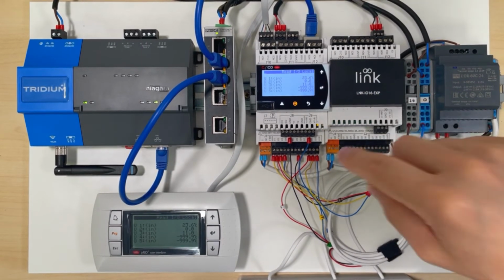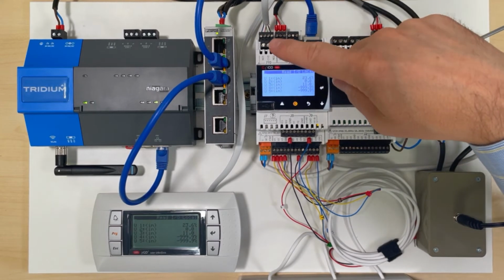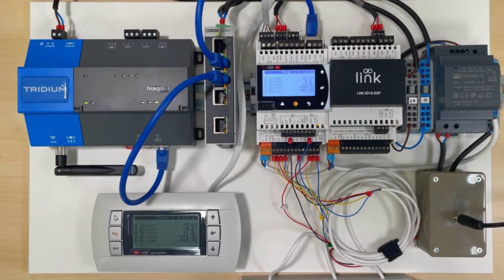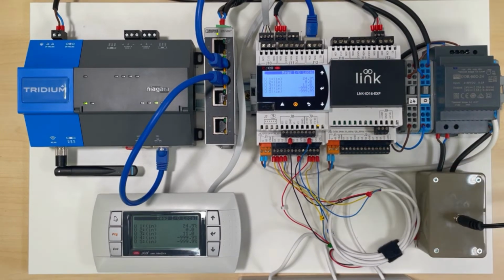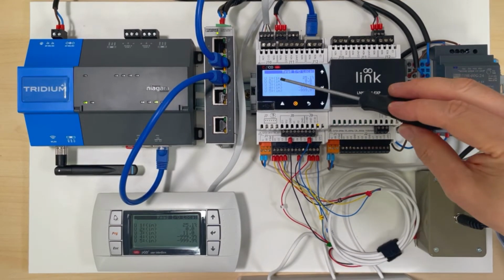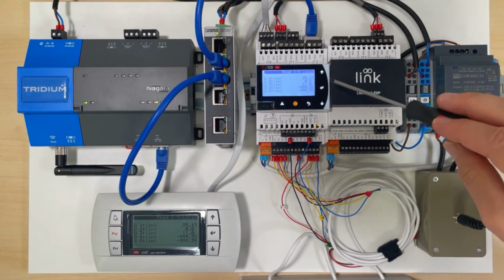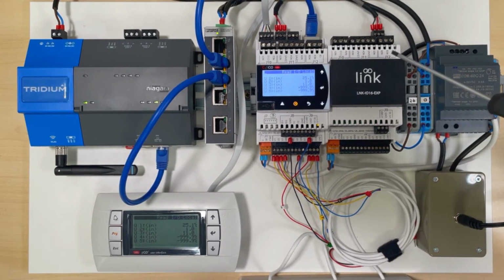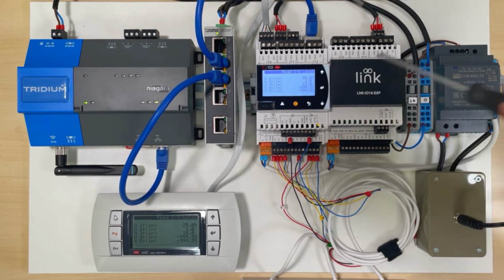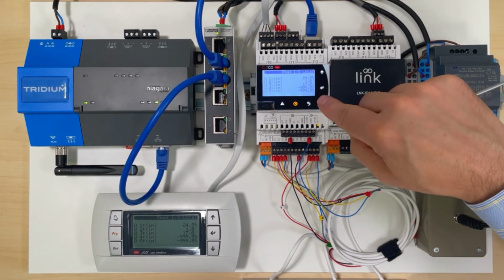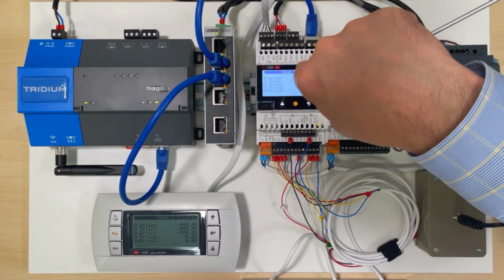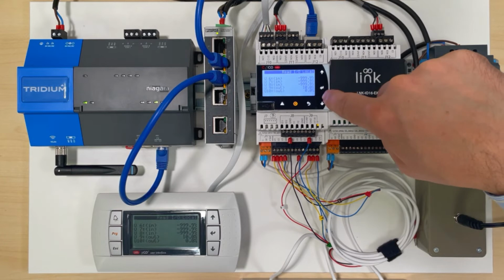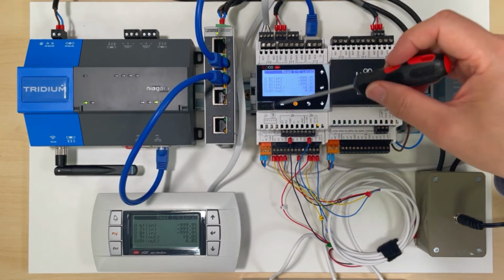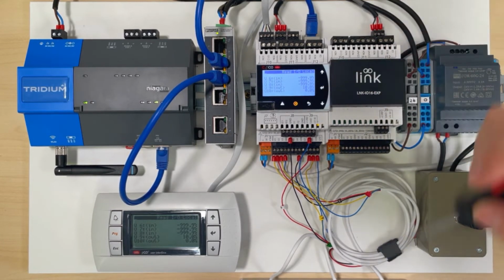So what you notice here is I've got U1 set up as 10K3A1. I could warm that up, and what you notice is it responds very quickly actually. I've got a U2 set up as a digital input, it's just on or off. U3 I've set up as pulse count, just put a few pulses into there and it will count up, and so on and so forth. If we go down, what you notice is in brackets against each universal I/O point, it tells you if it's input or output, so that's quite handy just to tell you what the function is.